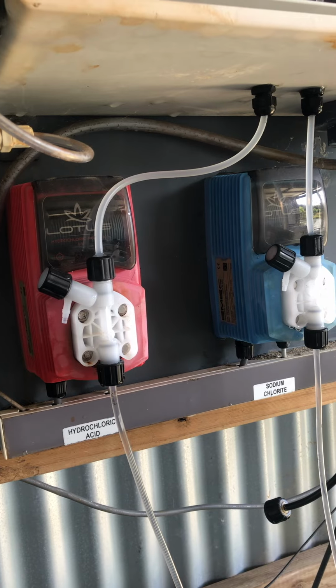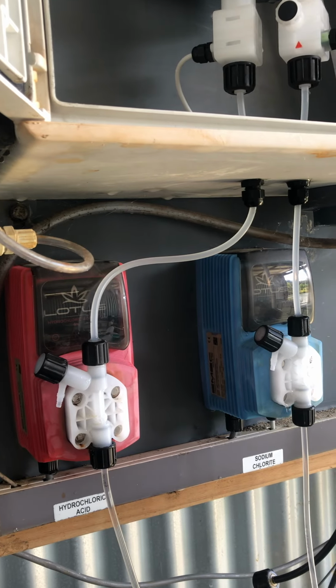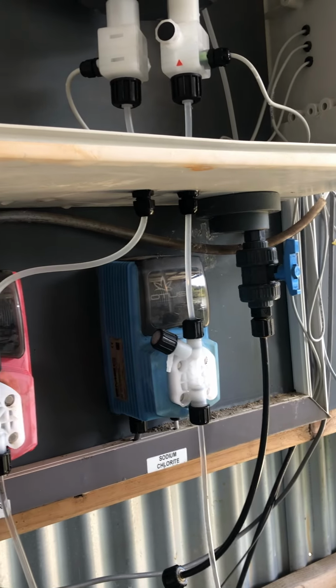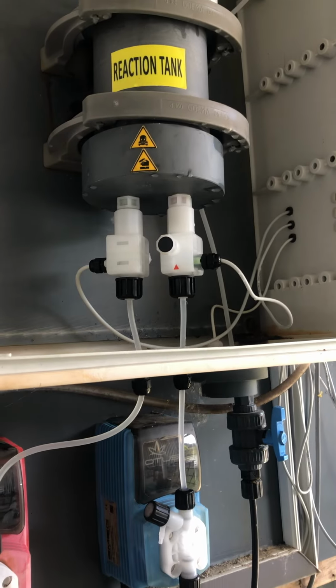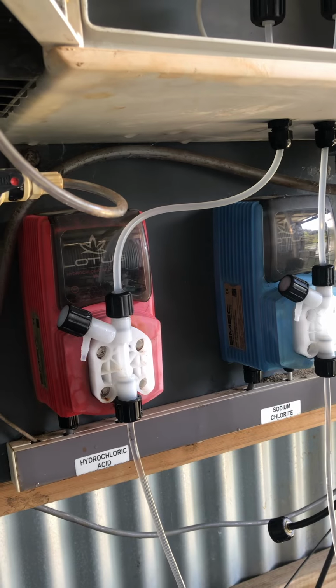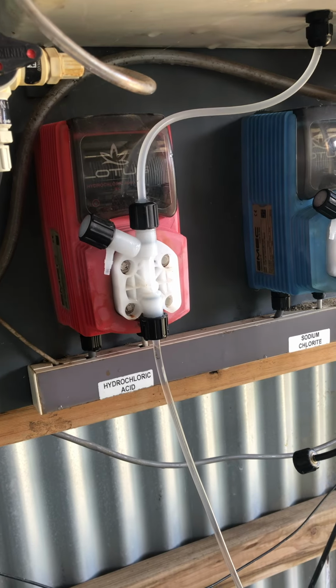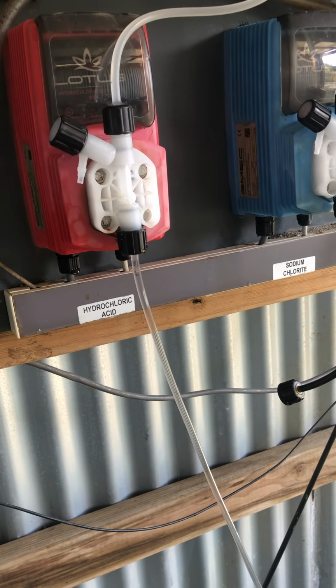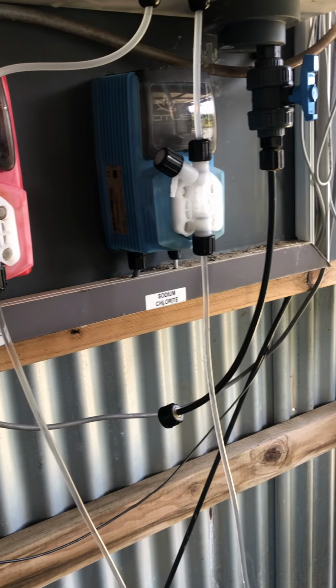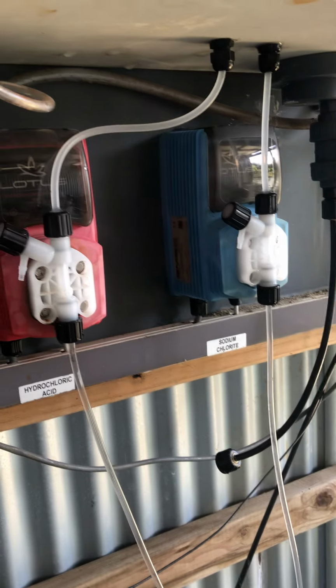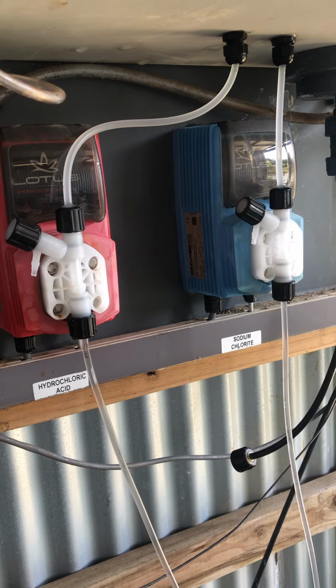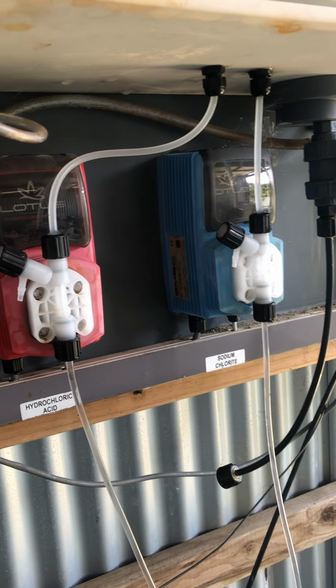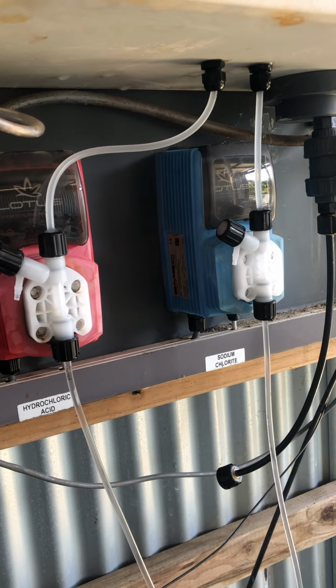Next stage I'll be doing is disconnecting the discharge lines, leaving this in place initially. This will be water, so it should be safe. Disconnect that, remove the pump head, and remove the suction lines, which are still only containing water. Remove the pump heads and replace them with new pump heads. Fit the new pump heads and then refit the tubing on the suction side.